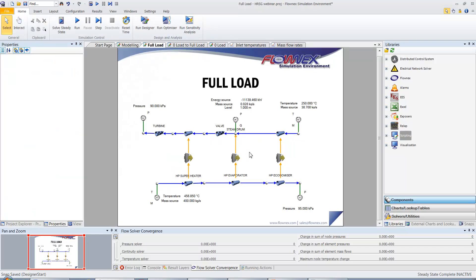The economizer, evaporator and superheater could now be connected. The flow resistance component upstream of the steam drum was removed and another one was added downstream of the superheater to represent a high pressure turbine.